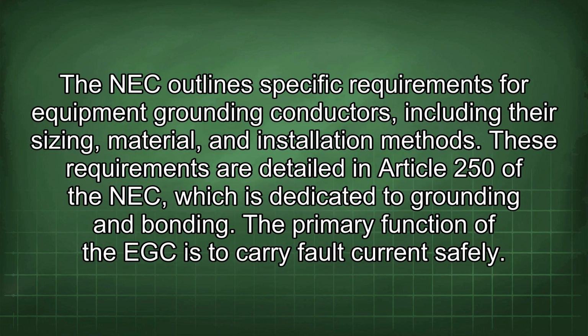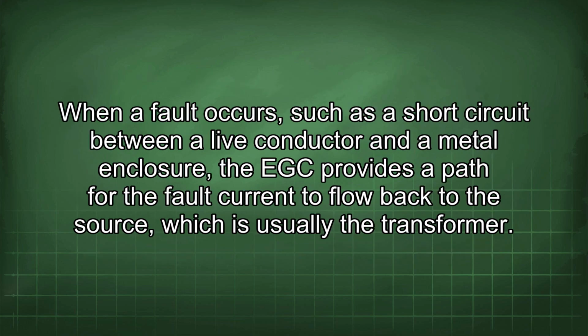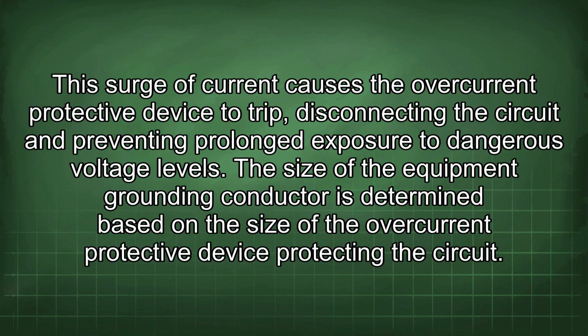The NEC outlines specific requirements for equipment grounding conductors, including their sizing, material, and installation methods. These requirements are detailed in Article 250 of the NEC, which is dedicated to grounding and bonding. The primary function of the EGC is to carry fault current safely. When a fault occurs, such as a short circuit between a live conductor and a metal enclosure, the EGC provides a path for the fault current to flow back to the source, which is usually the transformer. This surge of current causes the overcurrent protective device to trip, disconnecting the circuit and preventing prolonged exposure to dangerous voltage levels.